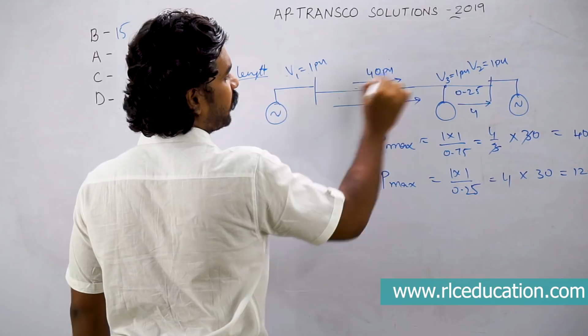Because this particular source which is maintaining here is just supplying reactive power. This is nothing but a STATCOM or a FACTS device. FACTS device is just a voltage source. It will just inject reactive power and try to maintain the voltage, but it will not supply or absorb any active power. It only deals with reactive power, and reactive power is nowhere concerned in our active power equation.